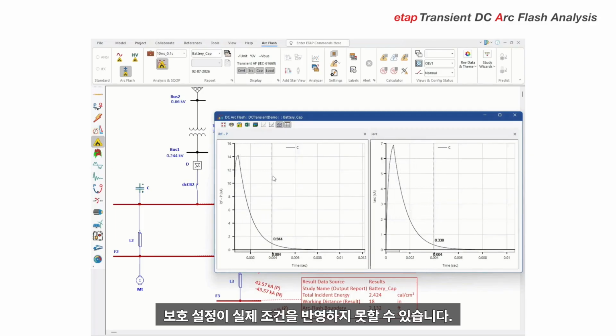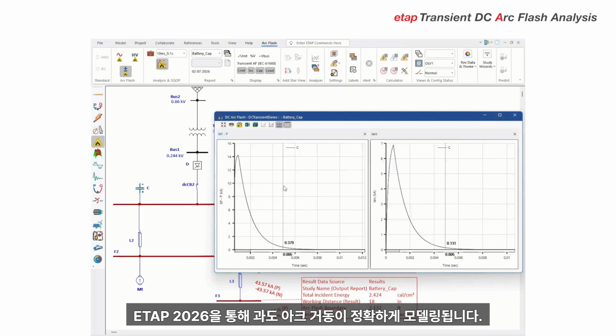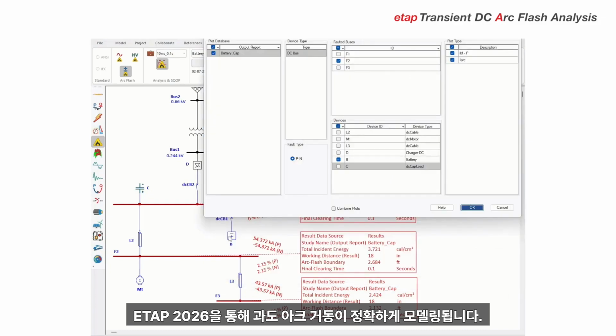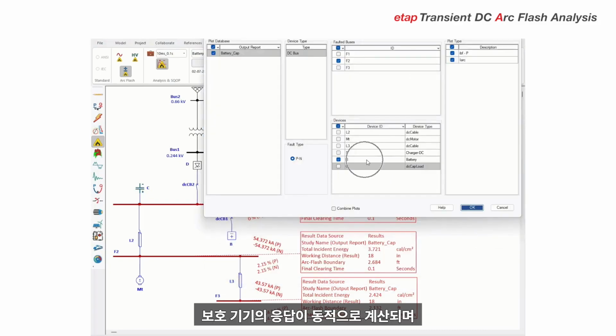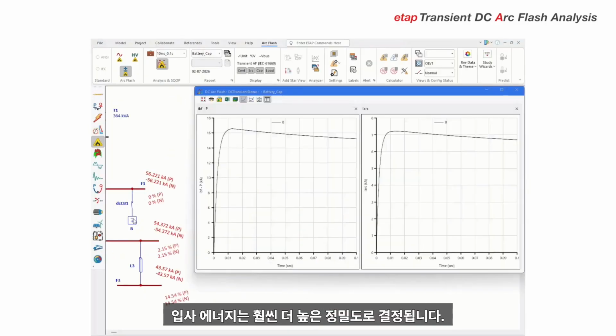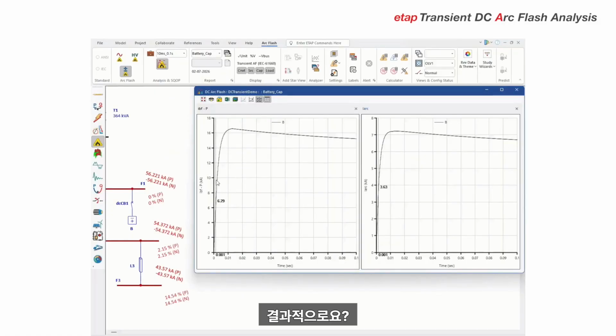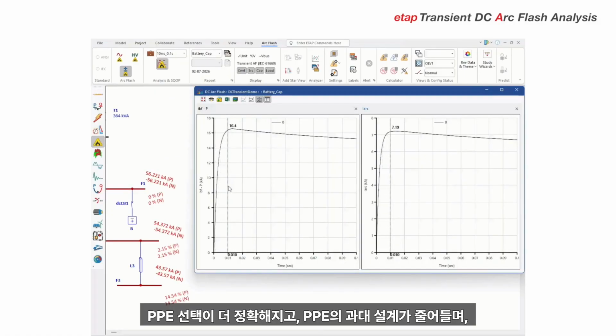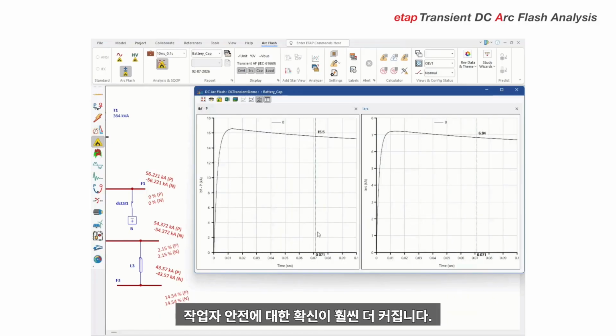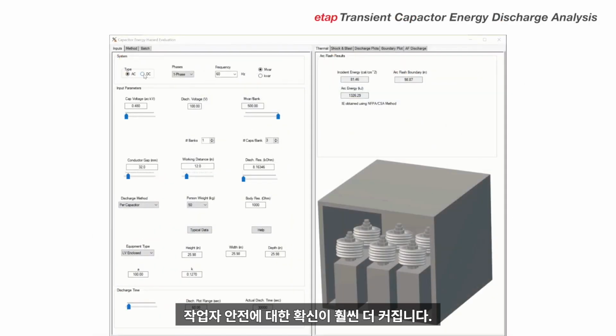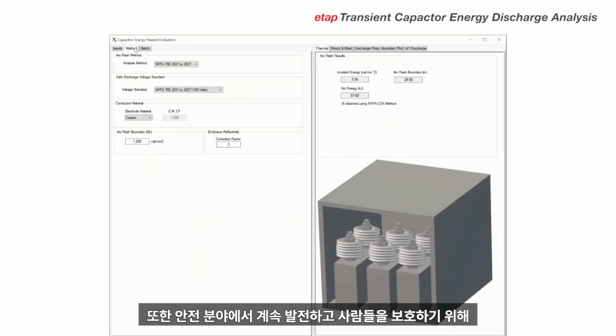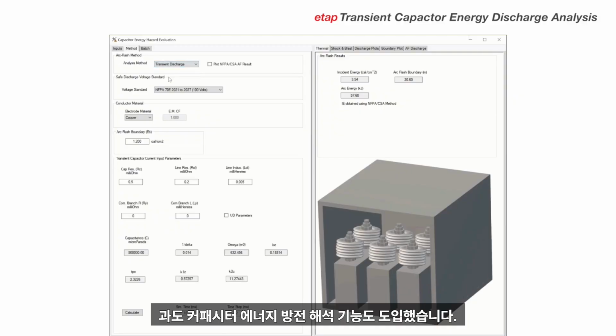real conditions. With ETAP 2026, transient arc behavior is accurately modeled. Protective device response is dynamically calculated. Incident energy is determined with far greater precision. The result? PPE selection is more accurate, over-design of PPE is reduced, and there is greater confidence in worker safety. We have also introduced transient capacitor energy discharge analysis to continue to push forward in the world of safety and to ensure people are protected.